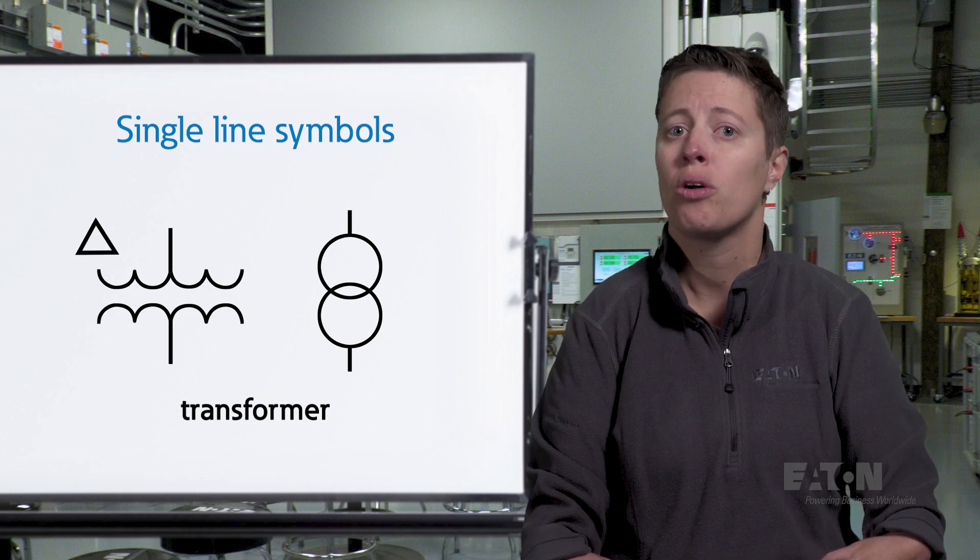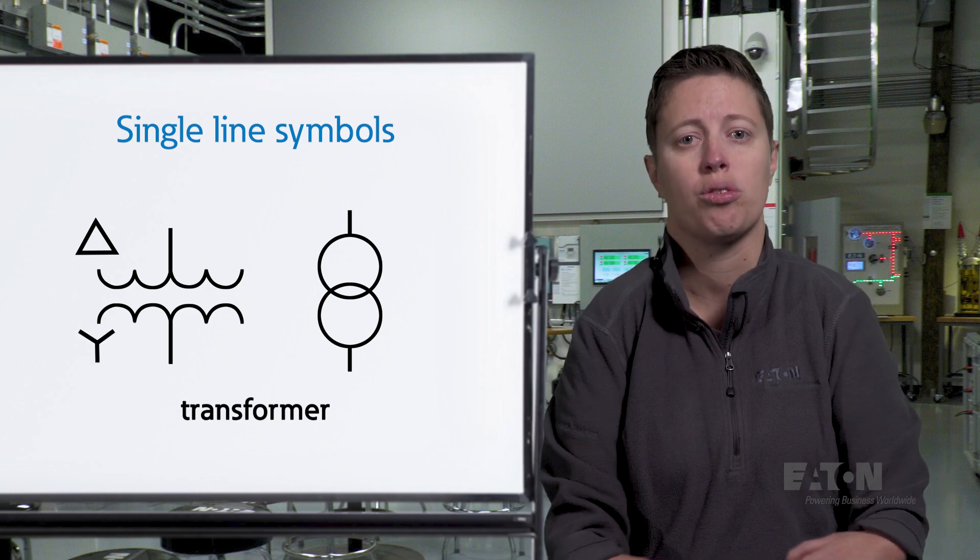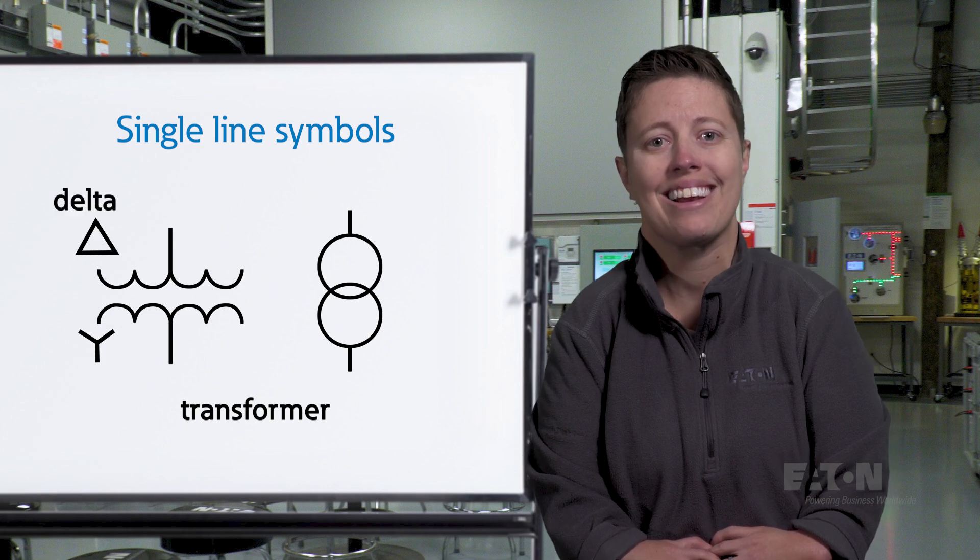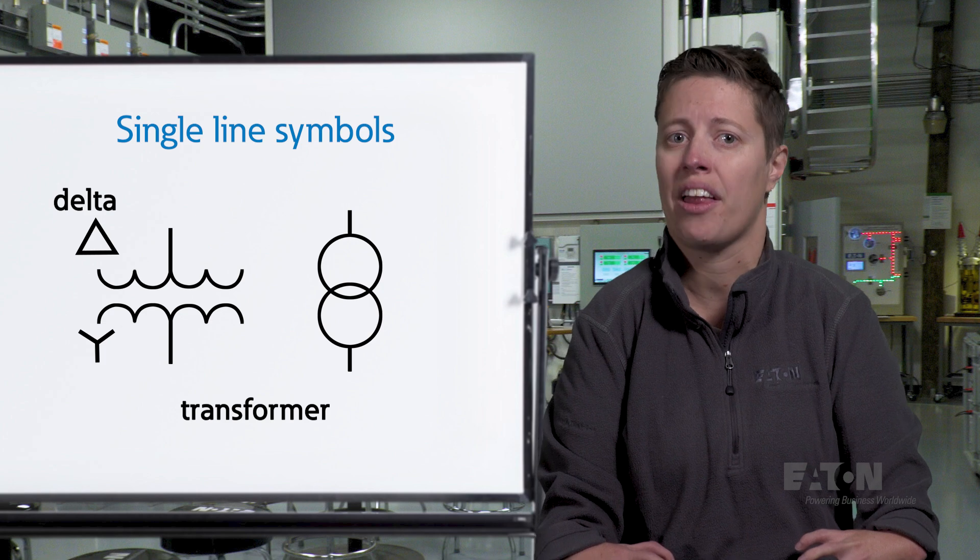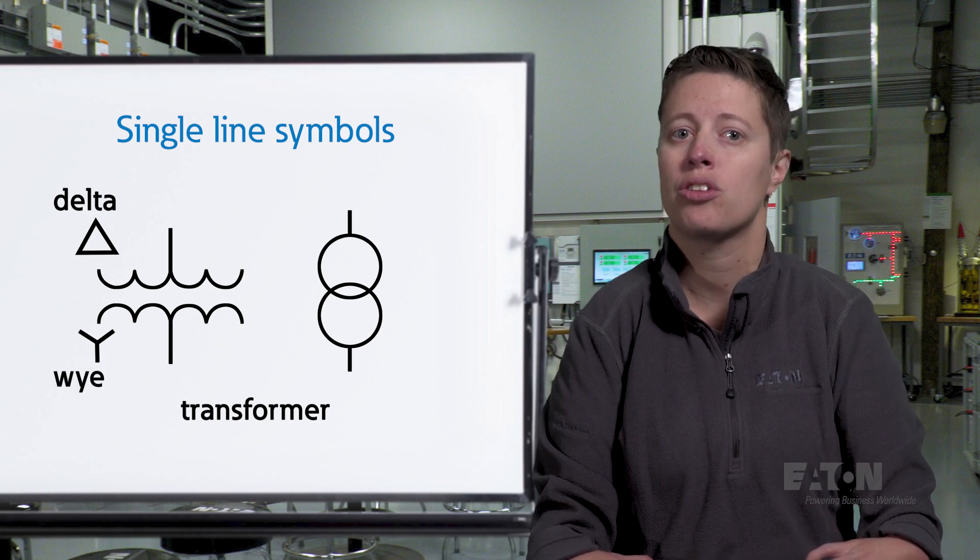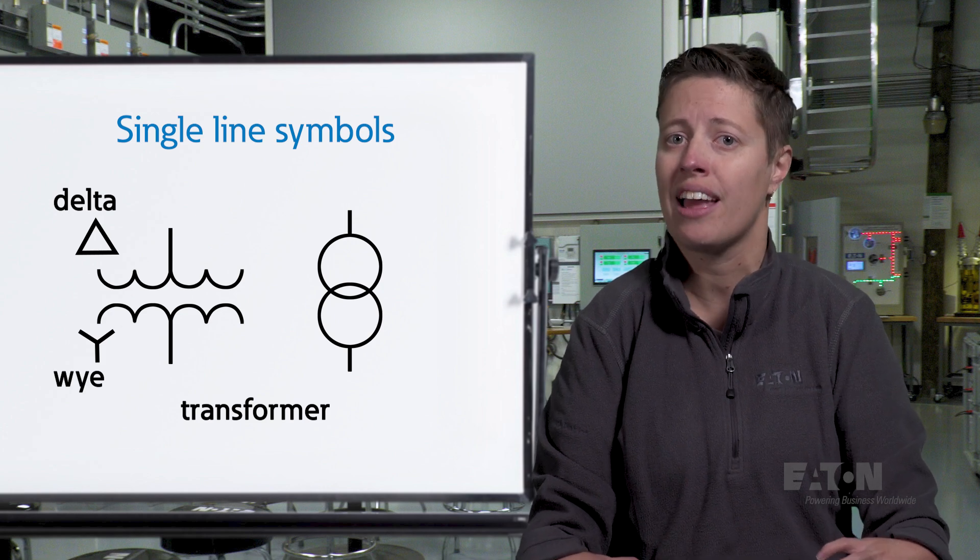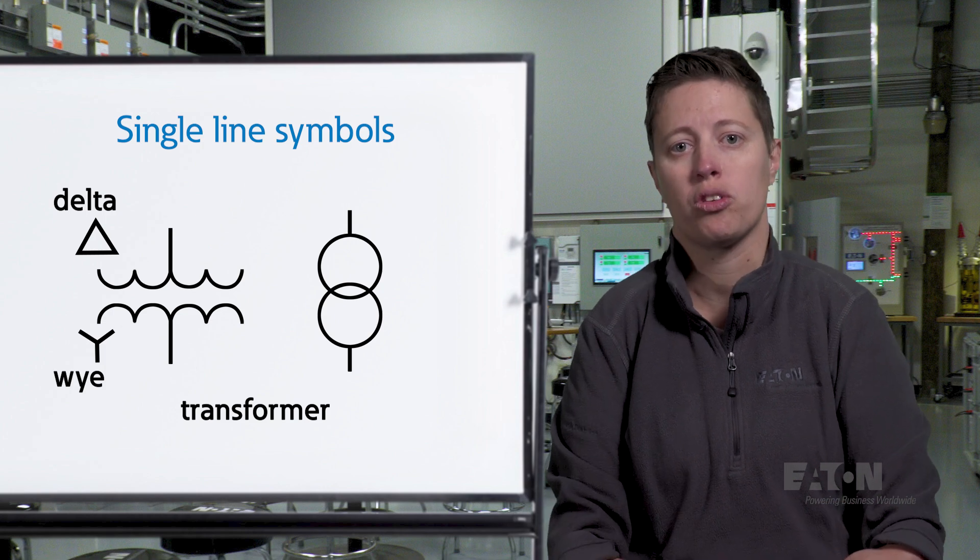You may notice a triangle or a symbol that looks like the letter Y along either side of the transformer. A triangle represents a transformer connected in delta, where all three phases are connected to one another, which resembles a triangle. A Y represents a transformer connected such that one end of each phase is connected to form a common neutral point, which resembles a Y.